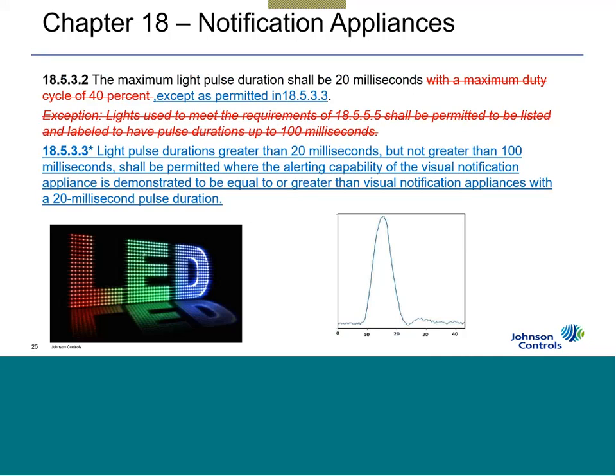Now, if you're looking at a device walking down a hallway, not so much a big deal. I can see the strobe right in front of me. But if you have your head down, you're working at your desk, and the strobe's behind you, you're looking for indirect viewing of the strobe being reflected off the floor, the ceiling, the walls to alert you. A slow ramp up and a slow ramp down may not alert you to that. And there are a lot of studies out there from NFPA to prove that out.